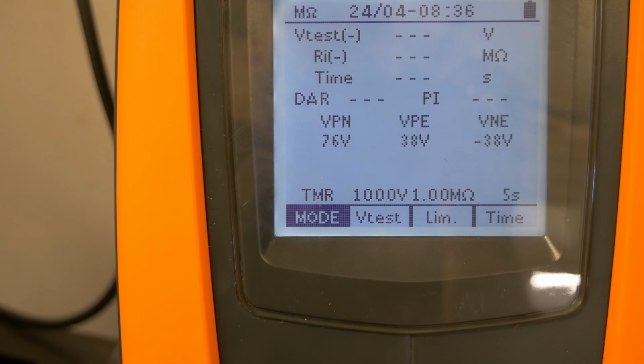It then comes out of the ProJoy into this DC isolator, which has the test probes in the top. Now these have been handily positioned to measure the voltage off the strings - you can see the ISO is doing that right now. We've got 76 volts or so being shown.